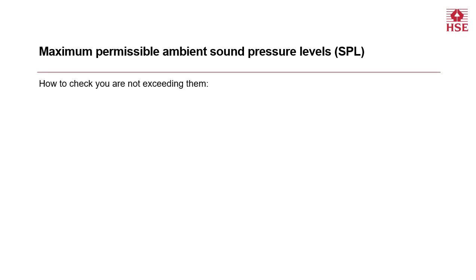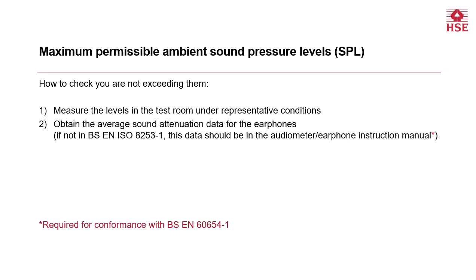So how do you check that you are not exceeding the maximum permissible ambient sound pressure levels? 1. Measure the levels in the test room under representative conditions. It is no good measuring the levels early in the morning when the building is unoccupied if the occupancy and the consequent noise levels are going to increase during the day when testing is occurring. 2. Obtain the average sound attenuation data for the earphones. If these are not in BS EN ISO 8253-1 already, this information should be in the audiometer or earphone instruction manual.